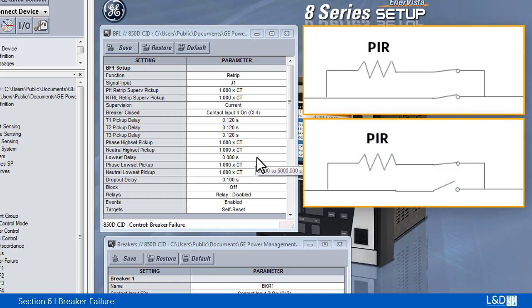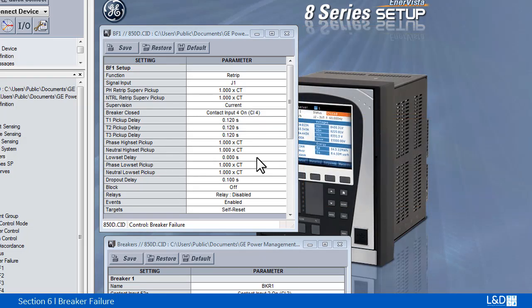The low set delay interval is the expected breaker opening time. Different breaker manufacturers have different designs of the PIR pre-insertion resistor. It is important to understand the sequence of PIR operation during opening before setting this parameter.